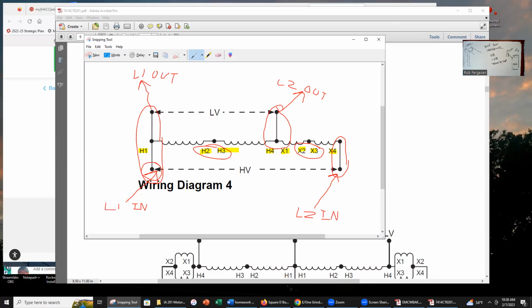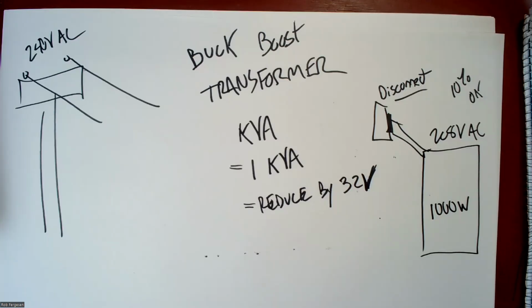One final note is sometimes with single phase power and even 3-phase power as well, you'll take one leg and then that one leg would be used against neutral or ground to give you 120 volts. So in this circuit, I have to be very careful that I don't try to use my leg 2 as a source for a 120 volt circuit, because it won't be. It'll be more like 90 volts. So that won't be good. So I have to make sure that if my machine over here on the right uses one of its legs for a 120 volt circuit, that the L1 is the one that I use. I don't use the leg that I've reduced.